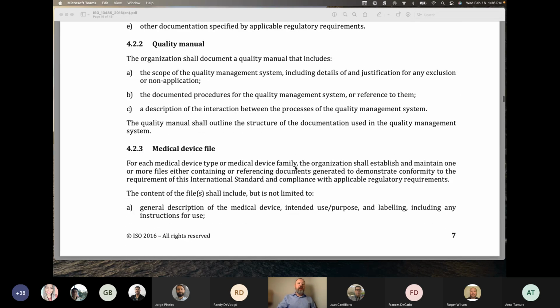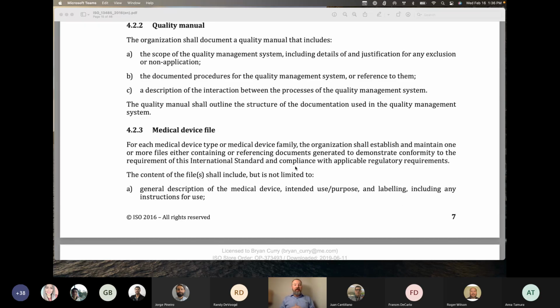Okay, moving into the specifics of the quality manual, 4.2.2, the organization shall document a quality manual, and that quality manual will include the scope of the quality management system. So again, going back to the building blocks that we started with in the introduction and in the earlier parts of section 4, there are portions of the standard that may not be applicable to your quality system. So the scope of your quality manual should identify anything that you are excluding or considering non-applicable, and you'll see it here, justification for why you're excluding it. Remember, the burden is on the organization to prove why they do not have to apply, or to prove why something is not applicable. Otherwise, the assumption is that it is applicable to your organization. I have seen sites get nonconformances because their quality manual did not make the appropriate exclusions.